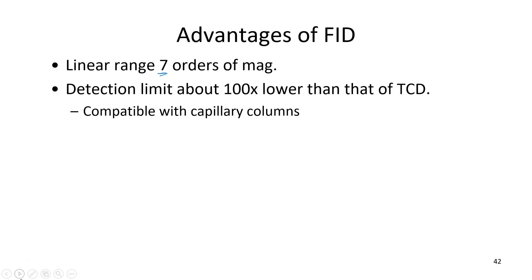The FID has quite a few advantages. It's got a really nice wide linear range and really nice detection limits, roughly 100 times lower than the thermal conductivity detector, making the FID compatible with capillary columns, which you may remember have a very low sample capacity.